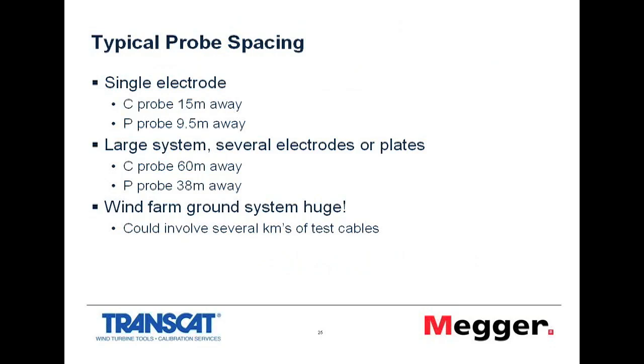Now, to be able to get that flat, I need to have the current spike far enough away from my ground system I'm measuring. And typically for a single electrode, I put 15 meters. I'm just trying to calibrate myself in feet here, but 15 meters would be a typical spacing for a single electrode. If it was a large system of a number of electrodes, or maybe a ground mat or a plate, we could be talking 60 meters. However, the challenge with wind farm ground systems is that they are often huge, especially as a complete wind farm.